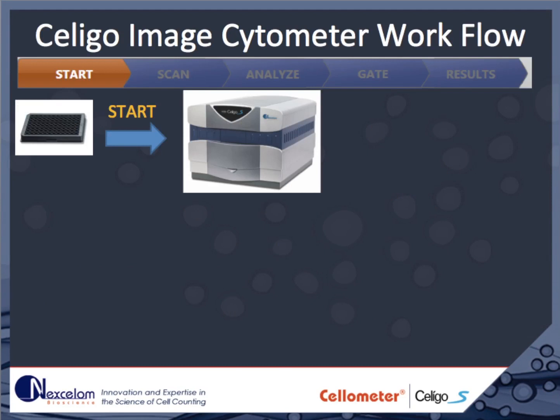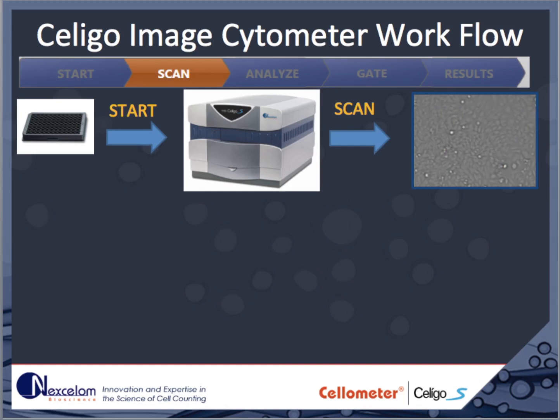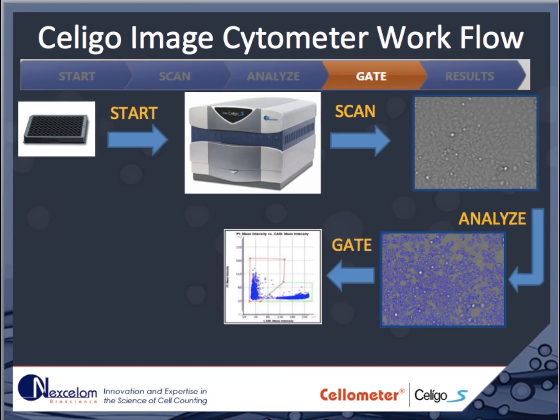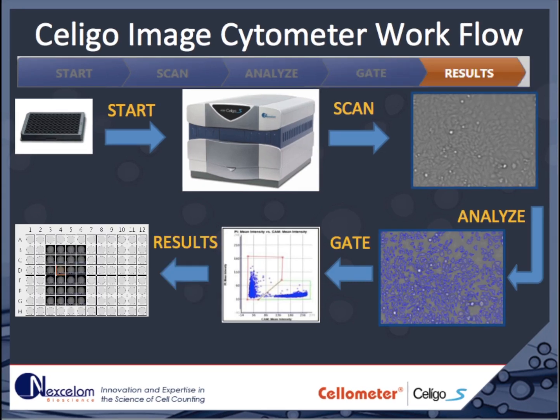Here I will describe the workflow of experiments performed on the Celigo. At the top of the slide, you can see the workflow progress bar, which is an element of the Celigo's user interface. First, assays are set up with the cells and treatments in a well plate. These are then placed in the Celigo, which begins to scan the plate in one or more channels. Following acquisition, the images are analyzed to detect the cells. The detected cells can then be further segmented into different populations using the FAC-Select gating interface. Finally, the numerical results are displayed to the user in the Results tab.